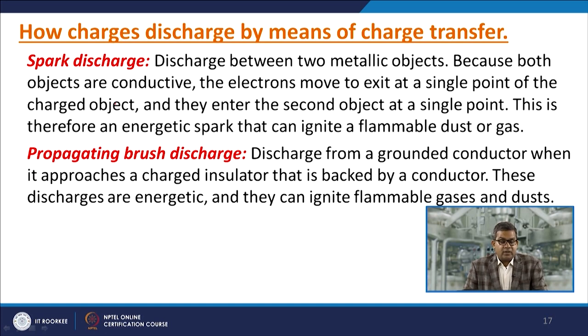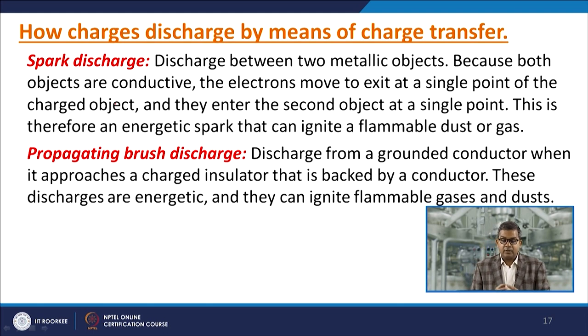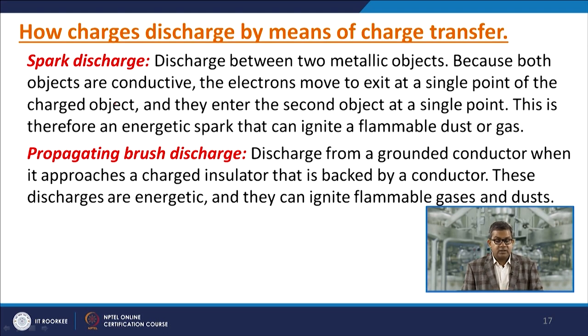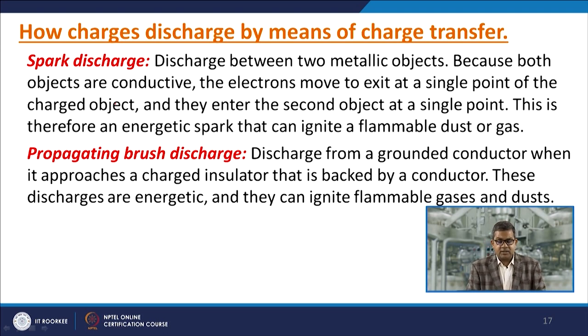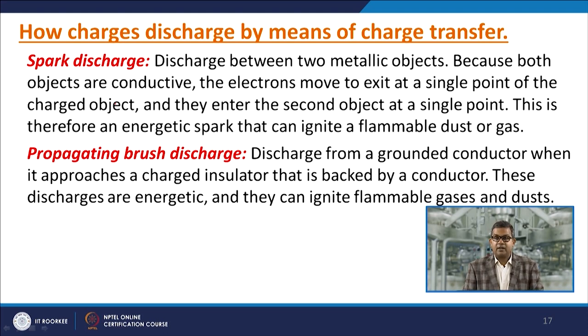Spark discharge occurs between two metallic objects since both are conductive. Electrons exit at a single point of the charged object and enter the second object at a single point. This produces an energetic spark capable of igniting flammable dust or gas. Propagating brush discharge occurs from a grounded conductor approaching a charged insulator backed by a conductor; these discharges are also energetic and can ignite flammable gases and dust.